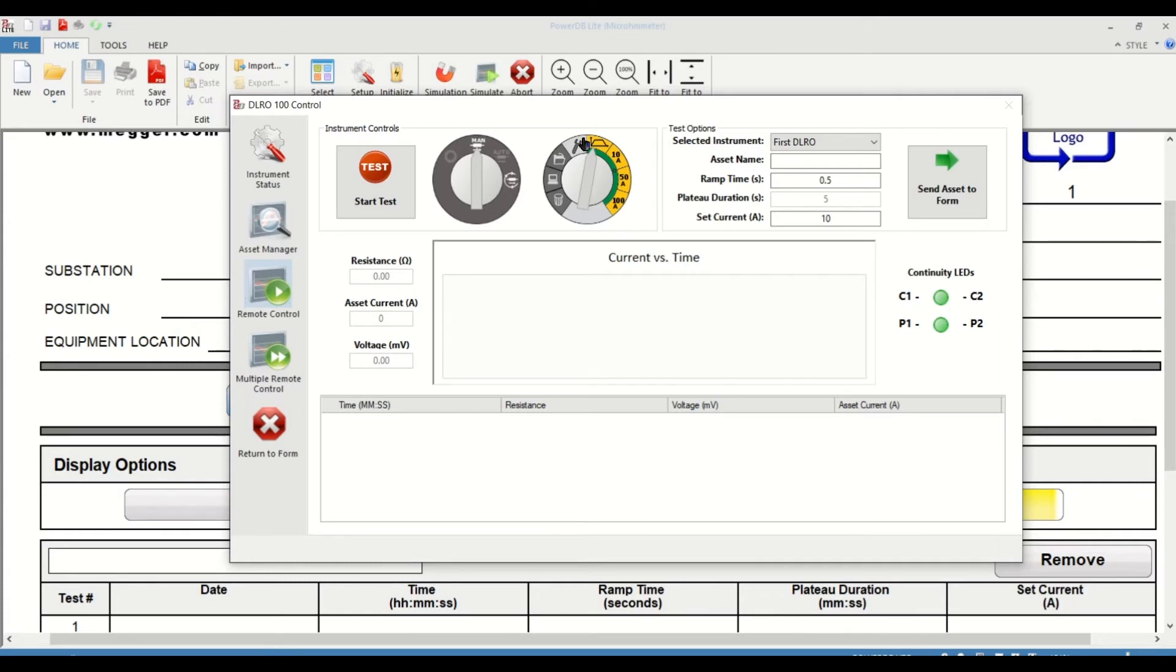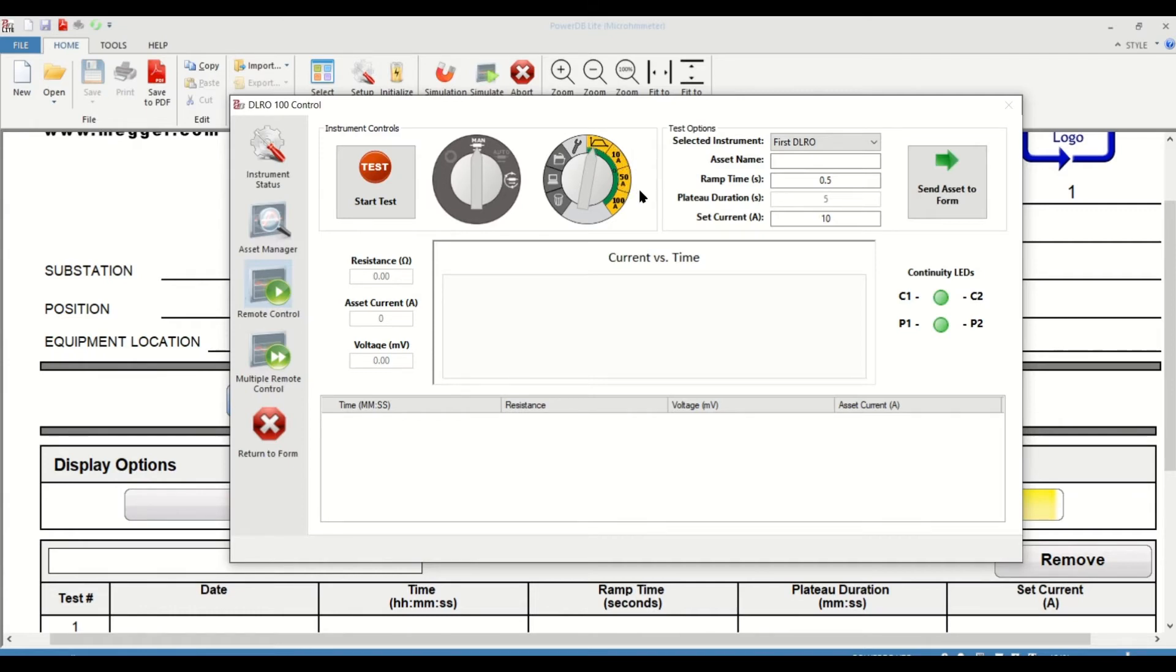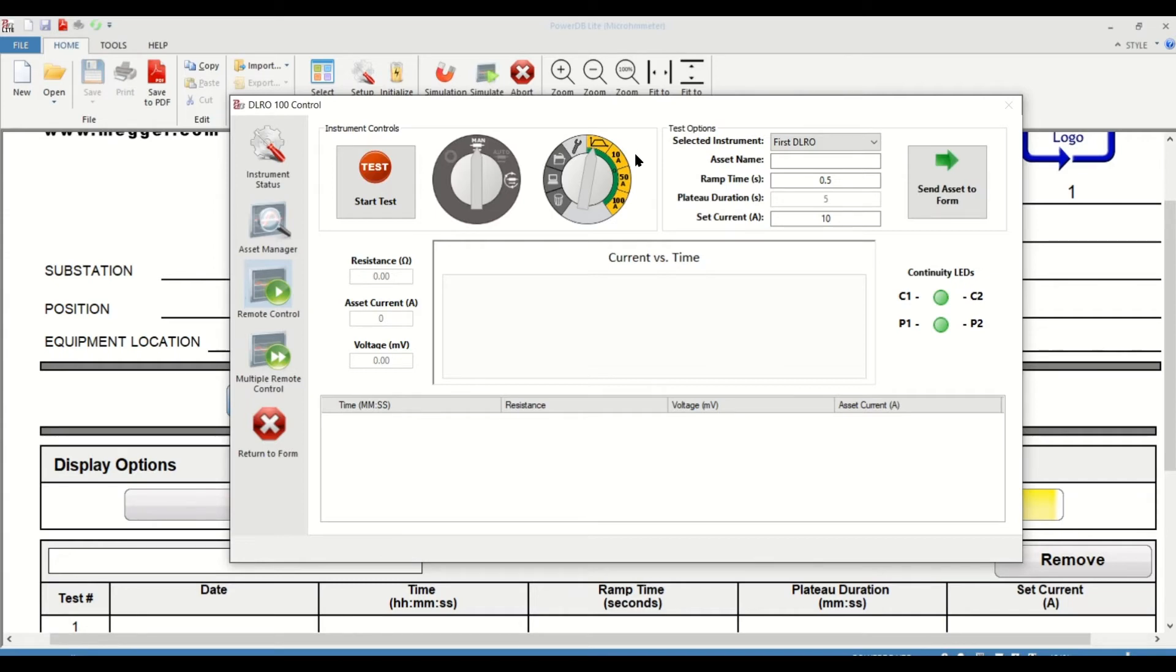And you also have the second rotary switch, which has only the testing side active. That is, you have the ramp that's active and then you have discrete magnitudes. In the ramp section, you can choose the ramp times and the magnitude of test current that you will be applying to the test specimen. And if you need preset values of 10 or 50 or 100 amps, they're readily available.